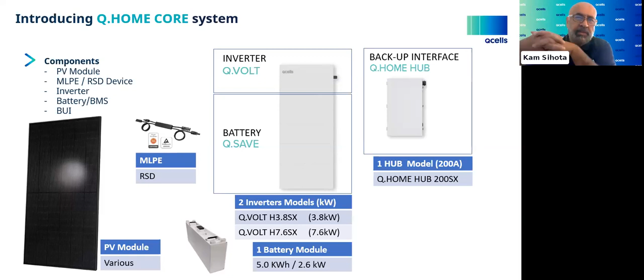Just at a high level, this is a picture on the right-hand side. Where the Qcells logo is shown, that block is the actual hybrid inverter, a bidirectional hybrid inverter. It takes the power from the modules and sends it to the battery, or from the battery to your load, your home, or to the grid, or from the grid to the battery. So all of that power flow is basically managed by this hybrid inverter.